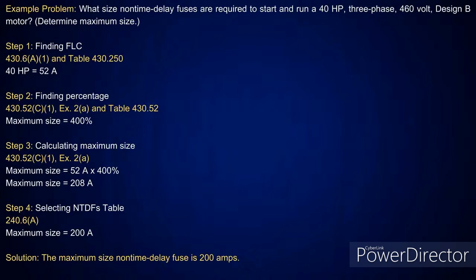Okay, so I'm looking at exception 2A. It tells me I can go to 400%. So I take the 52 amps at 400%, which gives me 208 amps. Once again, it says I can't exceed what? The calculated load. So the next size below that from Table 240.6(A) is going to be a 200 amp overcurrent device. Pretty simple.